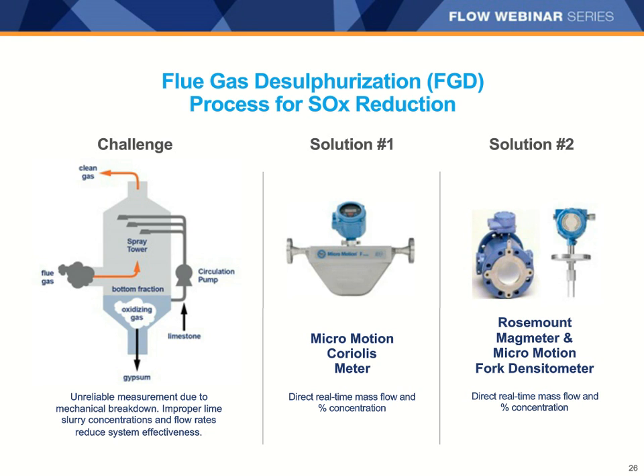First, you can use a Coriolis meter that can measure the mass flow rate and percent solids. Very tight flow control must be maintained in this method, or plugging or eroding of the tubes will result. Best practices dictate a velocity range of between 3 and 7 feet per second. If flow rate cannot be tightly controlled, a second method can be employed, using a magnetic flow meter in conjunction with a fork densitometer. These two devices will give you the desired flow rate and solids measurements needed for precise control. In addition, the low pressure drop across a magnetic flow meter reduces pumping costs in the process.